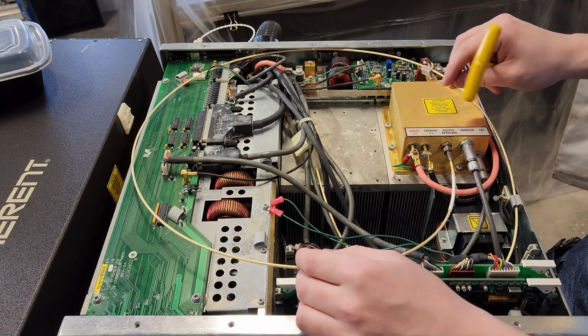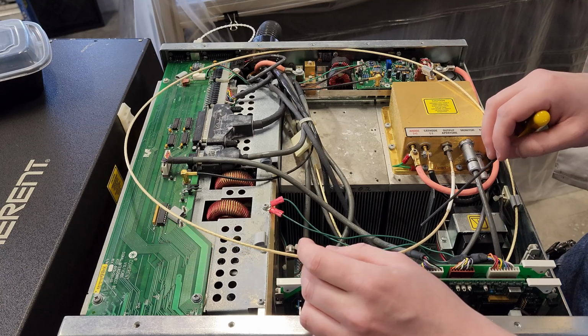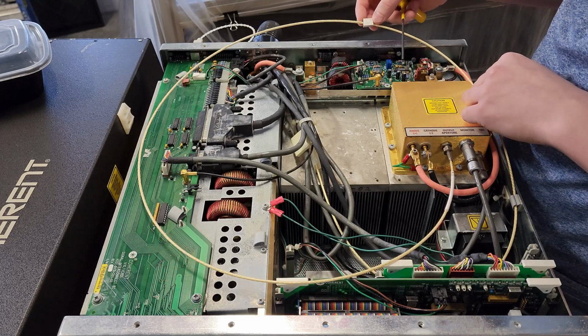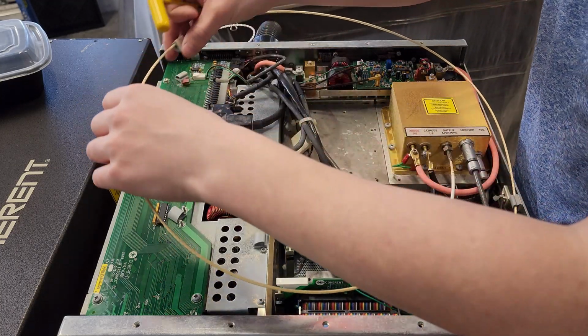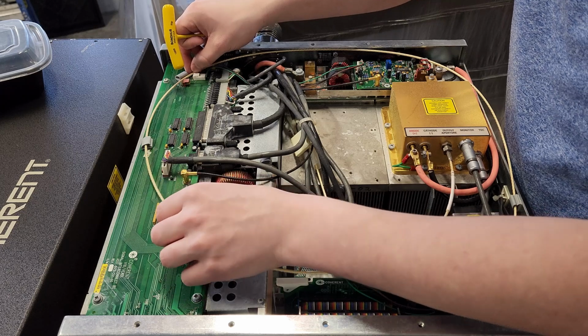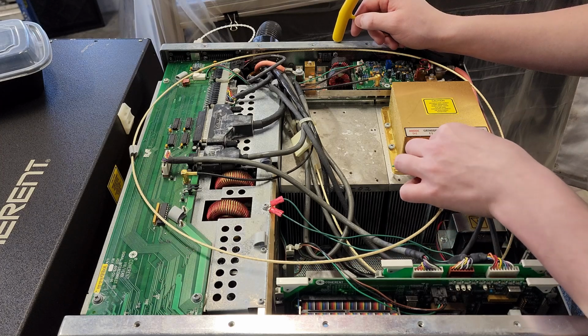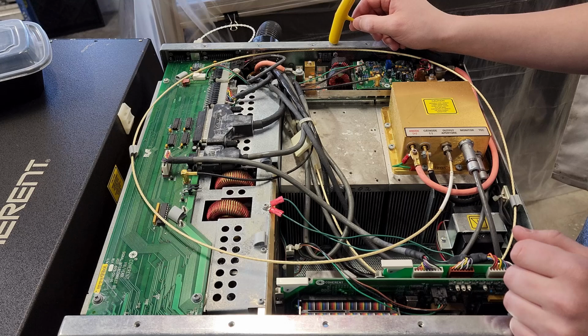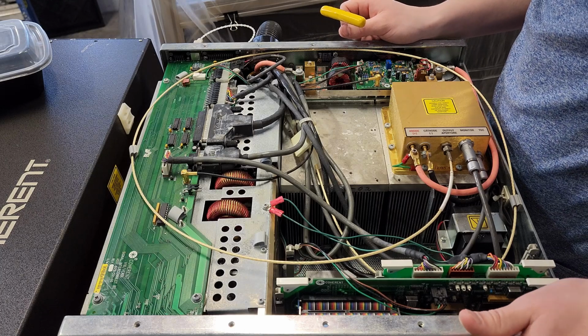So this is the diode module here, okay, and light is coupled out of this into this optical fiber, and through this optical fiber, you see someone's been in here and touched this at some point, messing with the fixed point on this fiber. This should be located probably here, I believe. And I'm thinking that this fiber should also be clipped into these points. So someone else has been in here and has looked at the output spectrum. Yeah, because this isn't properly tightened anymore. Someone else has messed with this thing. And it was not me. And that is a little bit concerning.